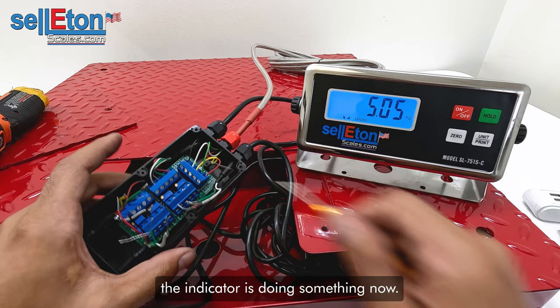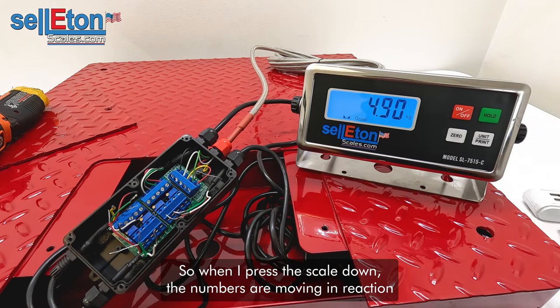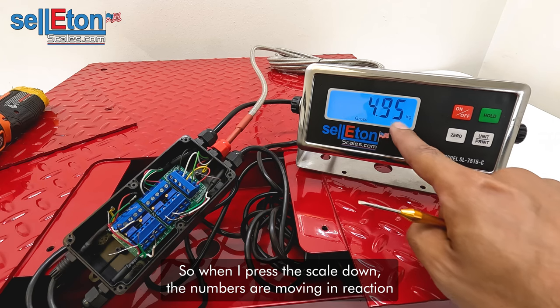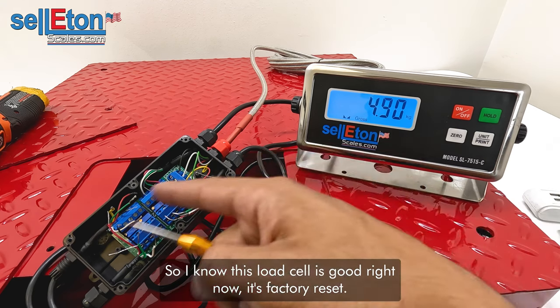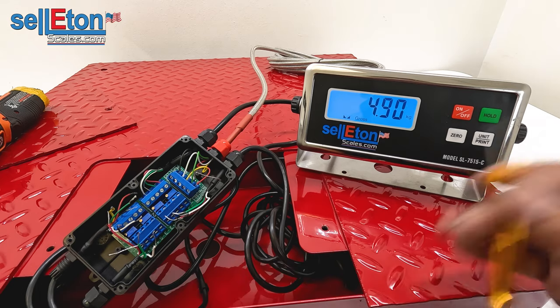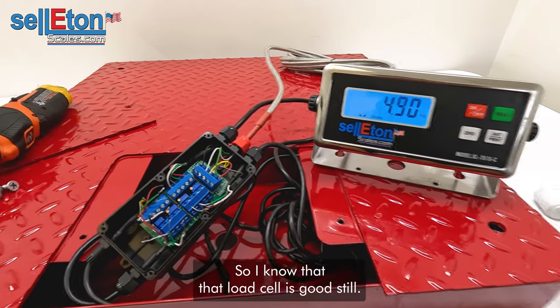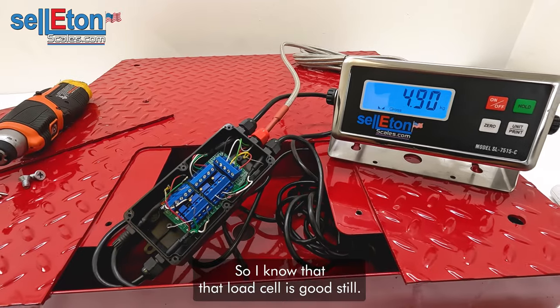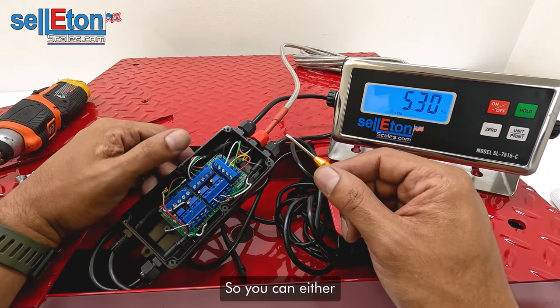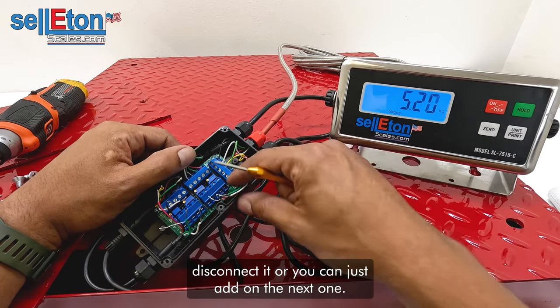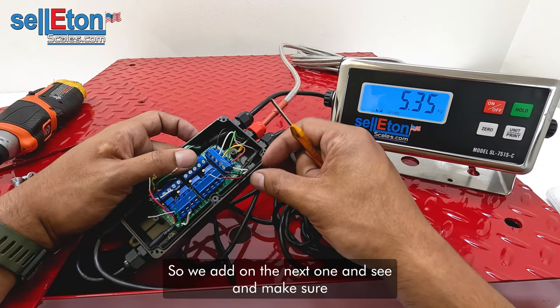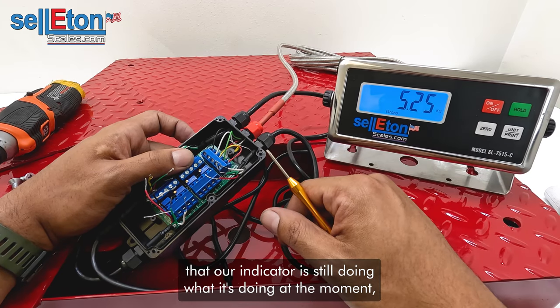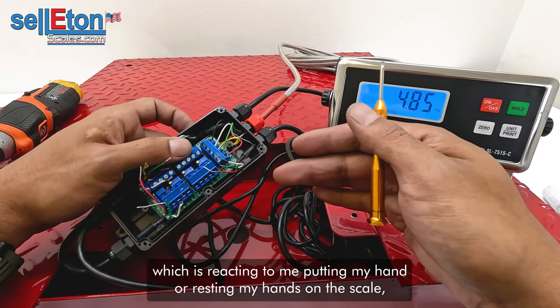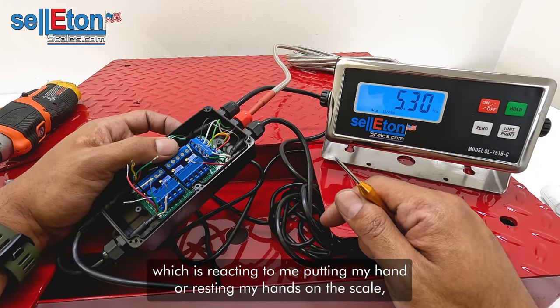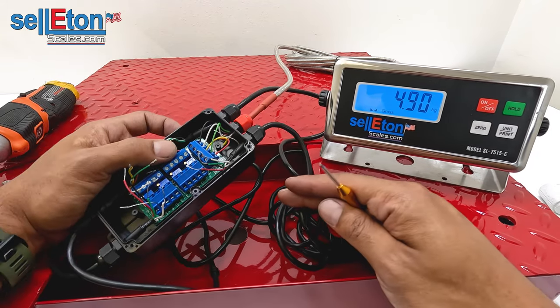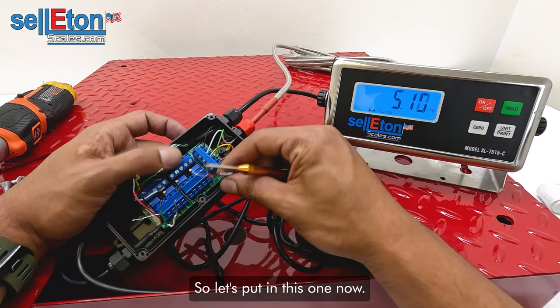So as you can see, the indicator is doing something now. When I press the scale down, the numbers are moving in reaction to me pressing the scale down. So I know this load cell is good. Right now it's factory reset, there's no good calibration on it, so I know that load cell is good still. You can either disconnect it or you can just add on the next one. So we'll add on the next one and make sure that our indicator is still reacting to me resting my hands on the scale and lifting them up, and it's consistent. So let's put in this one now.